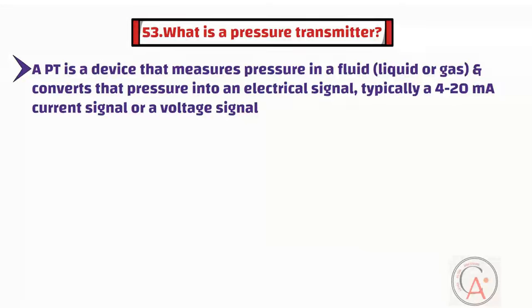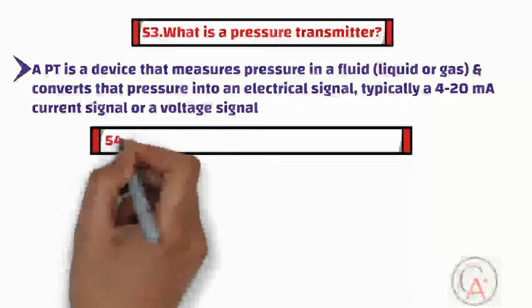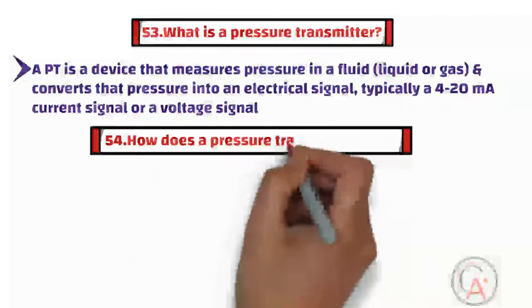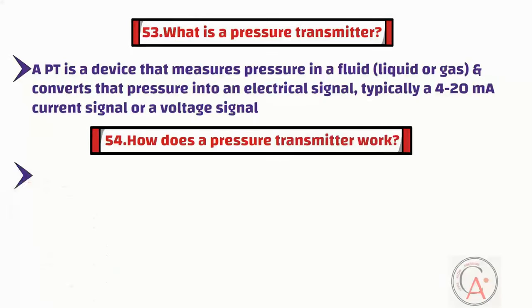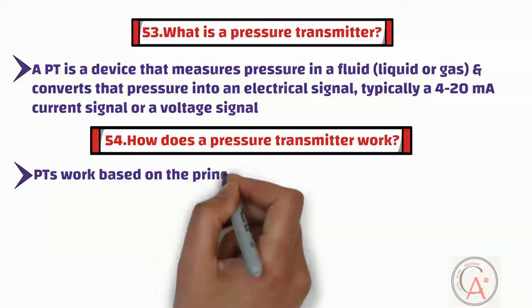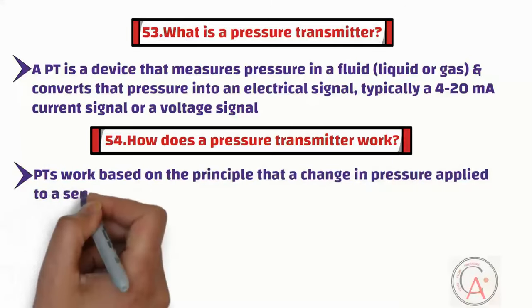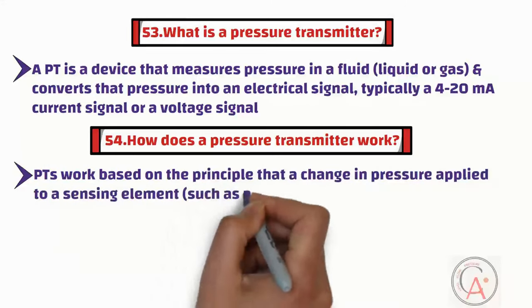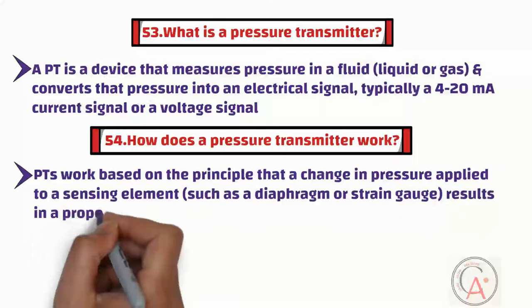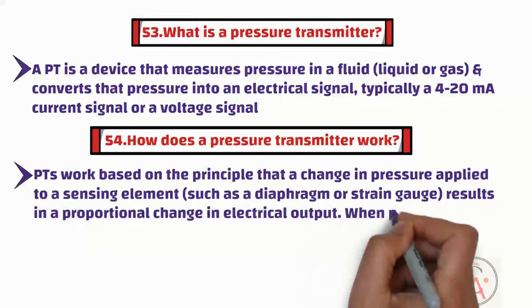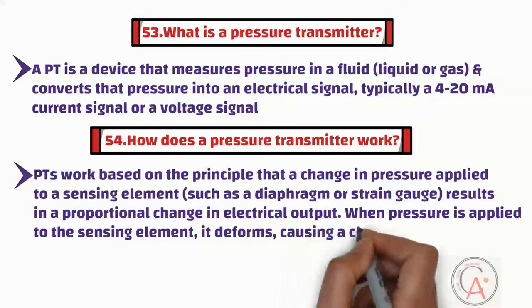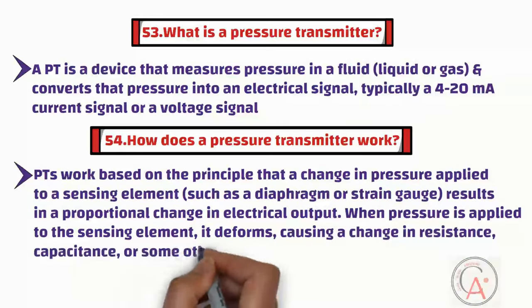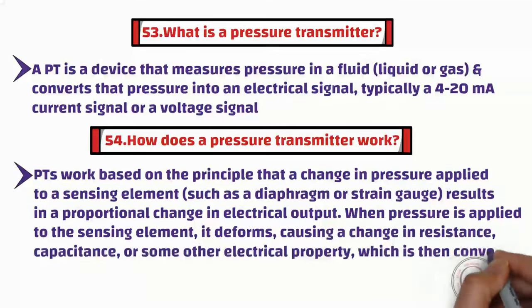Question fifty-four is: how does a pressure transmitter work? Pressure transmitters work based on the principle that a change in pressure applied to a sensing element such as a diaphragm or strain gauge results in a proportional change in electrical output. When pressure is applied to the sensing element, it deforms, causing a change in resistance, capacitance, or some other electrical property, which is then converted into an electrical signal that represents the pressure.